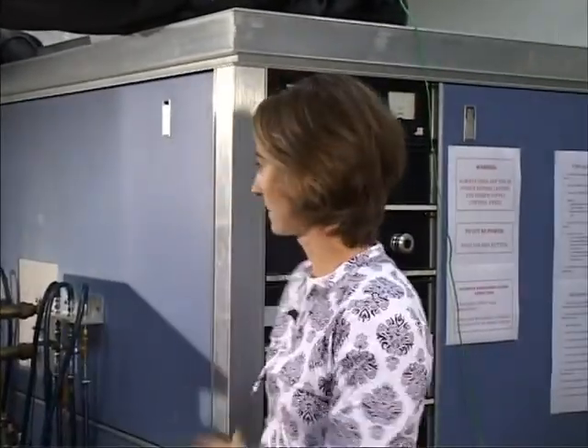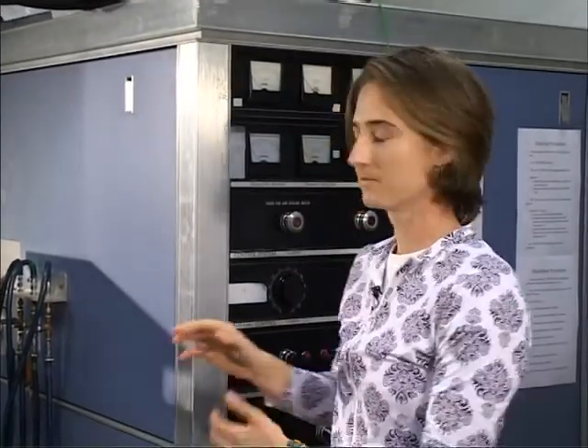This is the power supply that supplies power to the torch. The supply itself runs on 120 kilovolt amps and 50 kilowatts of that can be delivered into the plasma.